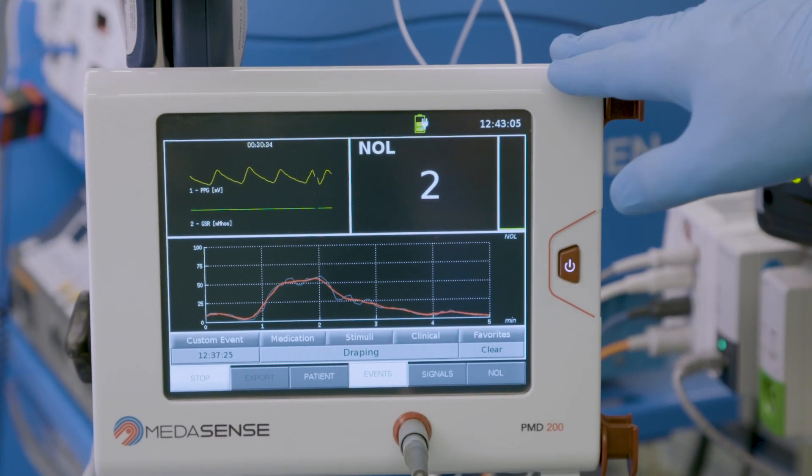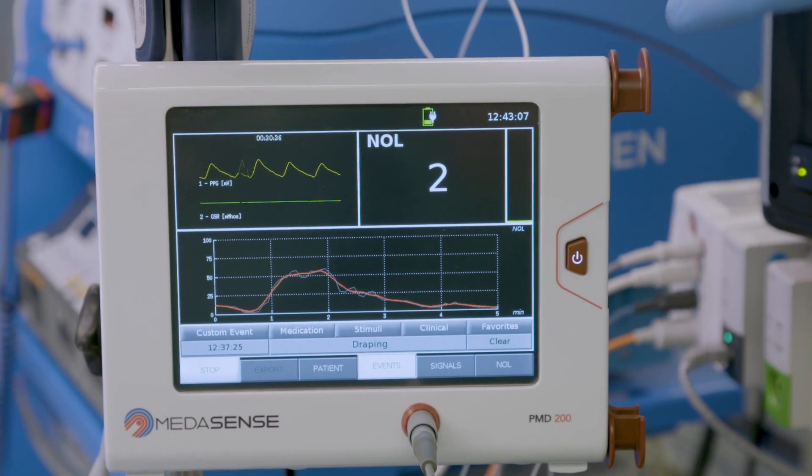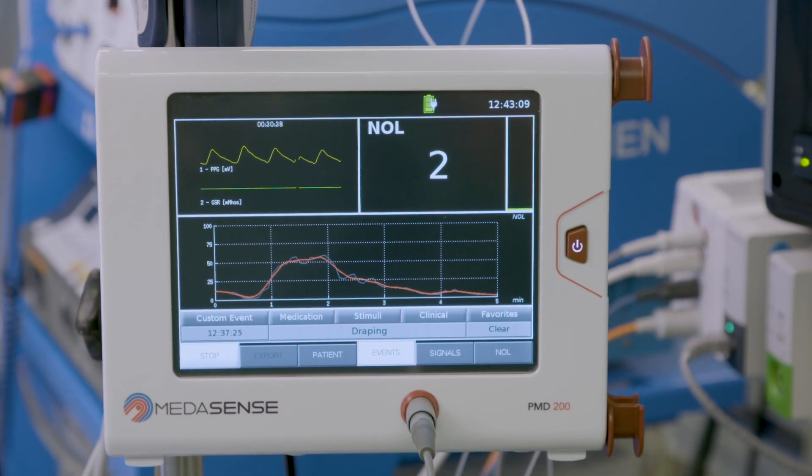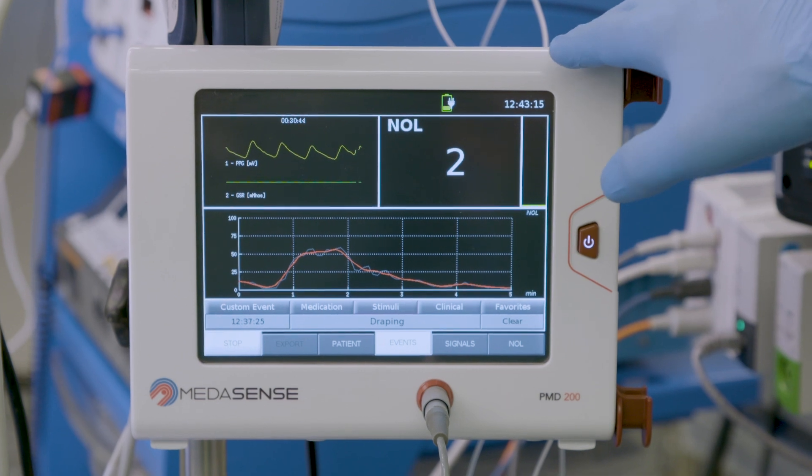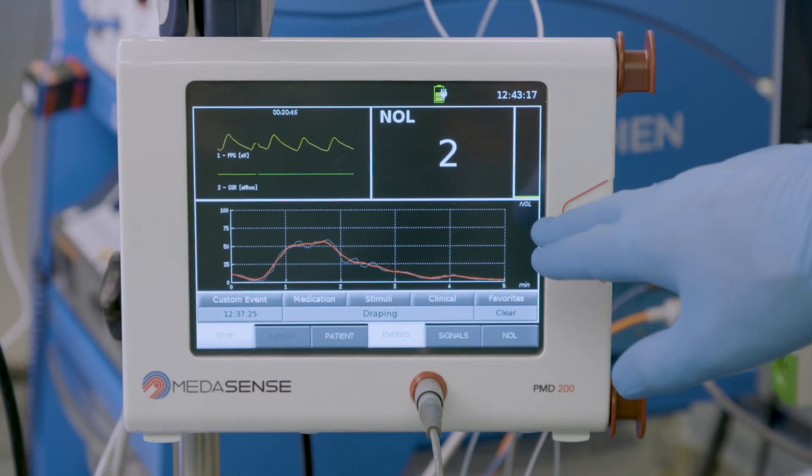I use NOL to optimize my drug titration. That means first I try to reach a reasonable level of hypnotic drug effect. I often measure it with a bispectral index monitor and I try to have a range between 40 and 60, and only once I've reached that steady hypnotic level, I evaluate the NOL and then I start adapting my opioid titration in order to have a good range of effects.